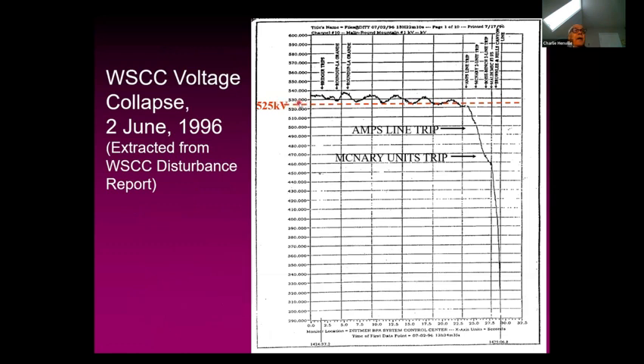So it's a 500 kV transmission system, and it's operating above 525 kV for most of the time. And then this scale down here is in seconds. So this is 5 seconds from this point to this point. So within 10, 15, 20, 25, all of a sudden you got a very fast voltage collapse.